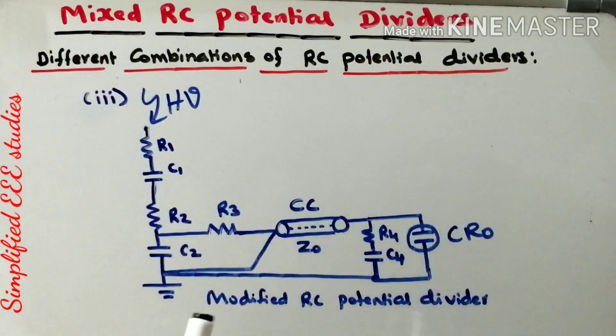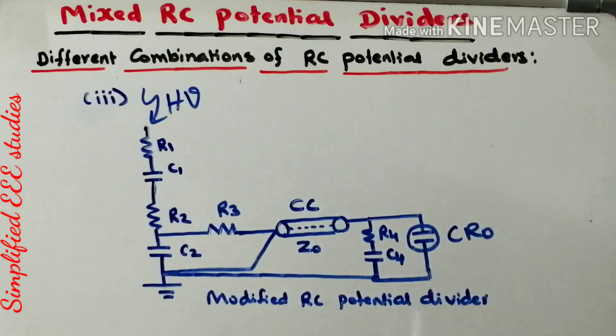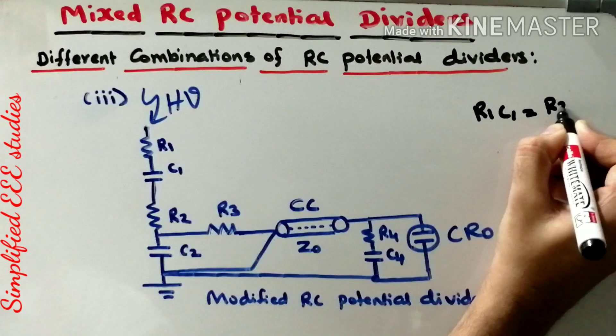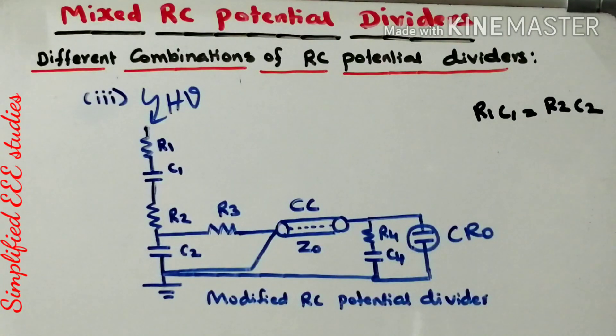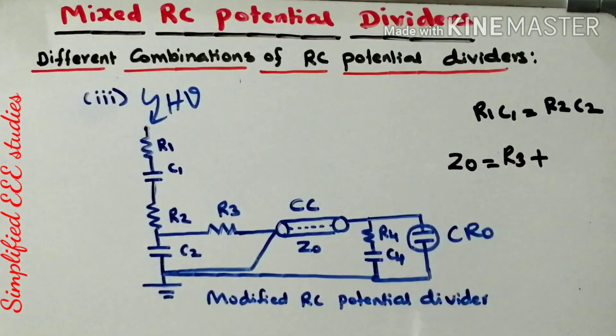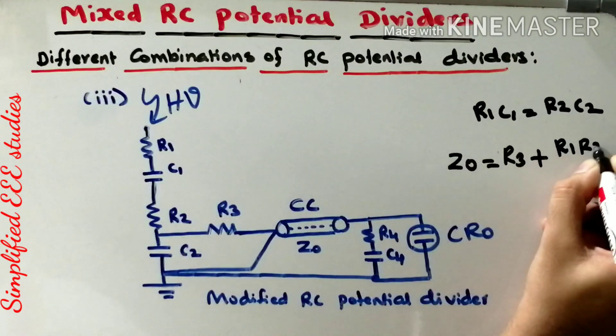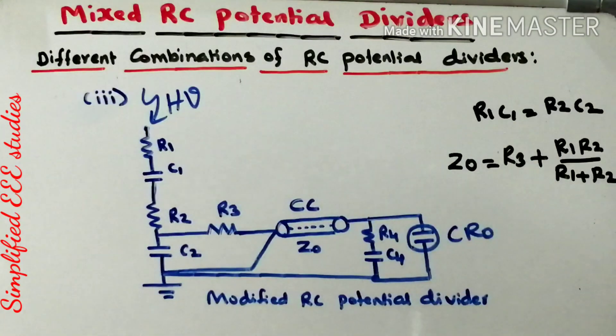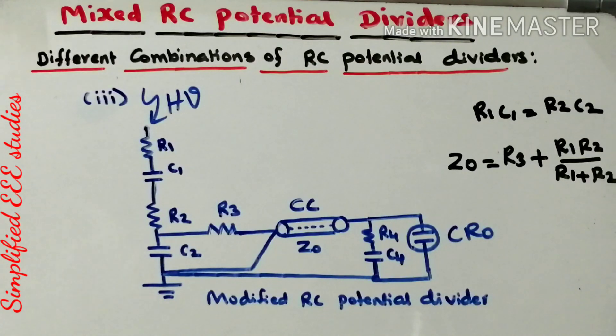The third combination is known as the Modified RC Potential Divider. It again improves the step response and is a modification of the RC series type potential divider. It obeys the relation R1·C1 equal to R2·C2. The surge or characteristic impedance can be calculated as: Z0 equals R3 plus (R1·R2 divided by R1 plus R2). This helps predict the characteristic impedance of the coaxial cable.